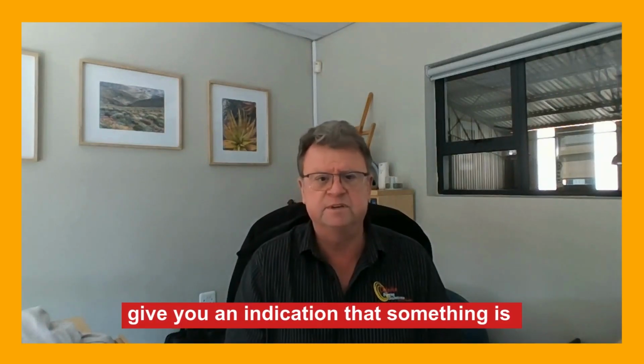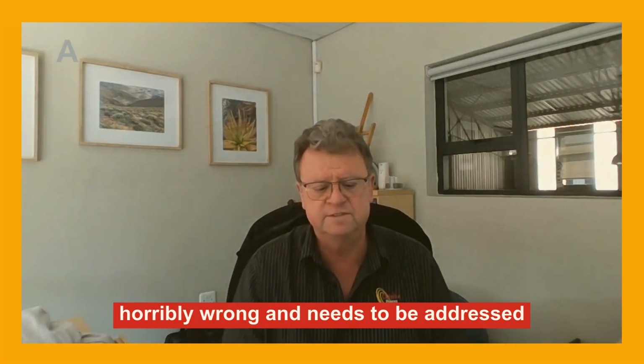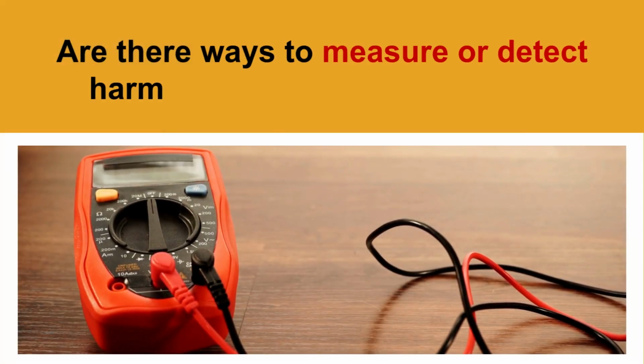Usually when the harmonic content is very high, you will see a number of strange symptoms at a particular site. Things that don't make sense, where things trip and you reset them and everything works again. Things overheating that shouldn't be overheating. There are usually a number of symptoms that will give you an indication that something is horribly wrong and needs to be addressed.